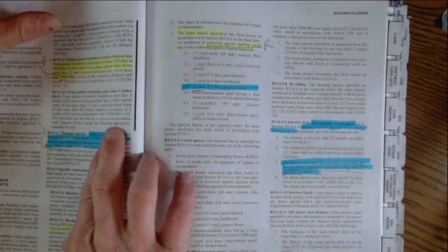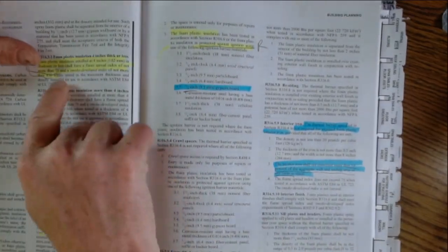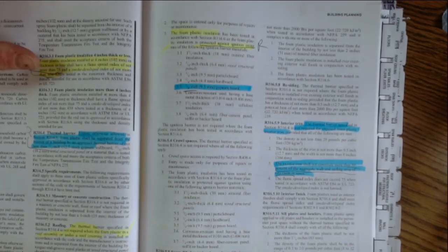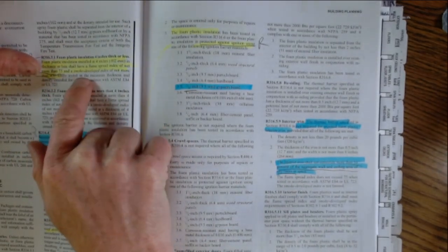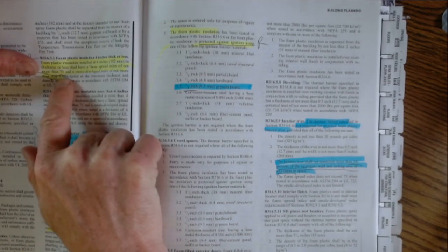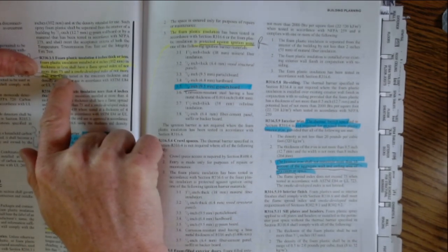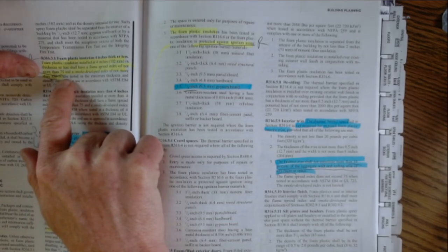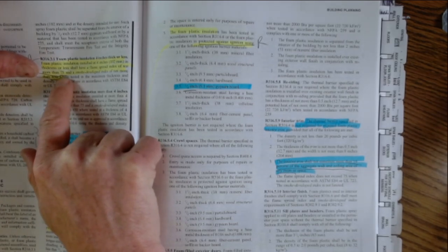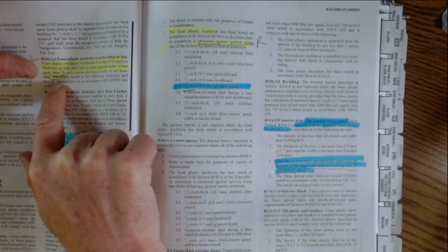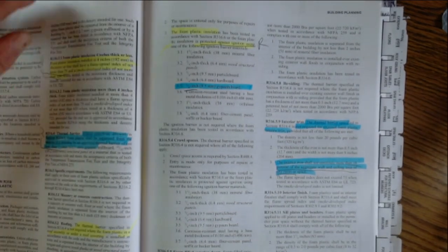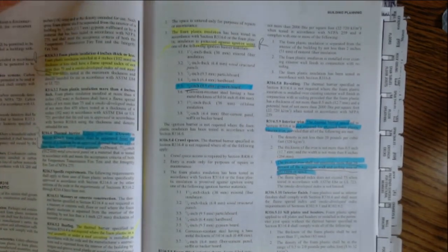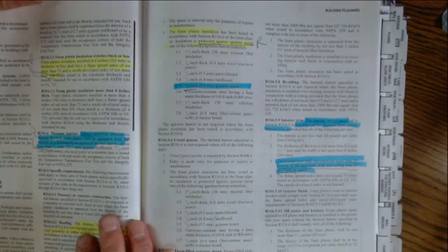Foam plastic insulation. This is different than the commercial piece. This is a flame spread index of 75 based on the Steiner tunnel test, ASTM E119. Or no, hold on a sec. Oh, ASTM E84. So it's 75 there. Everything you're going to see is smoke index of 450. They've just defaulted to 450 because it works for everything. There's no reason to change it.